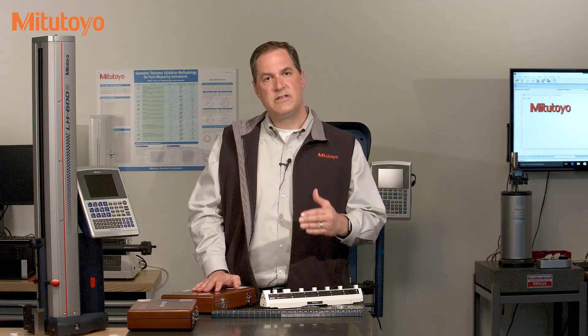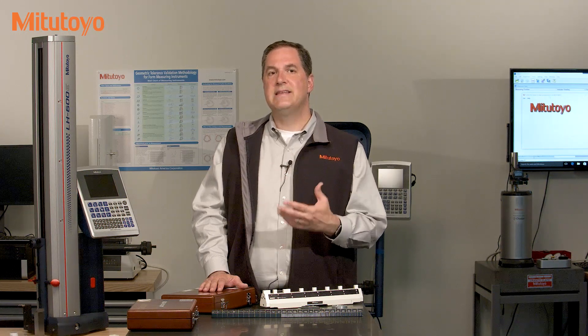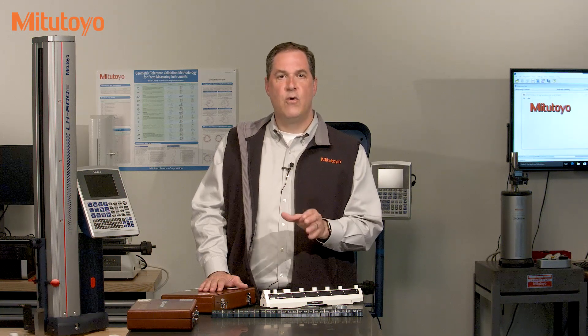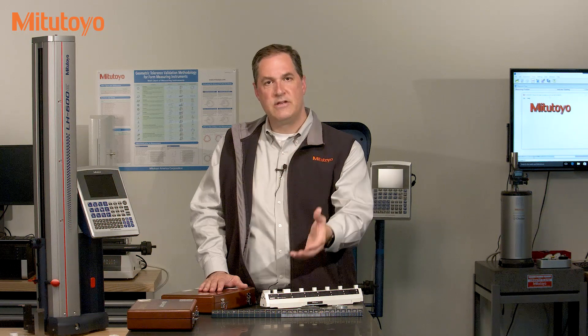The CMC is also sometimes called the best measurement capability. Now we're not getting into what uncertainty is in this episode. But let's just say that a lower uncertainty or a lower CMC means the lab can measure more accurately. Scopes are pretty powerful and a very easy way for you to vet calibration suppliers. Or as I like to do, to spy on my competition.